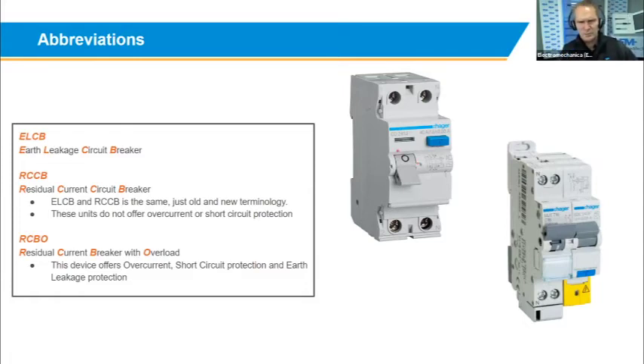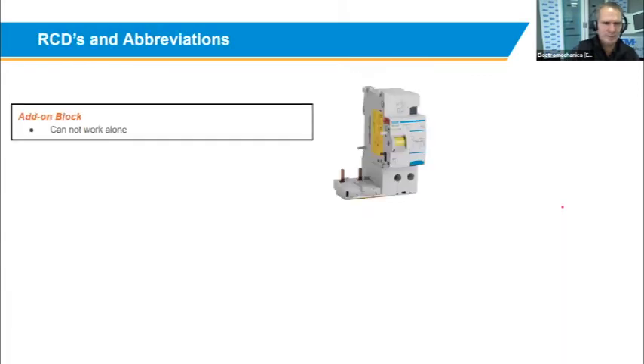Also, just for interest's sake, an earth leakage device does not have a kA rating as such. It does have a withstand rating. So you still need to put a circuit breaker in to protect it from short circuit. So an RCBO, as I said, is a residual current breaker with overload. It's something similar to the unit on the right. This is just the add-on device, which I will get to on the next slide.